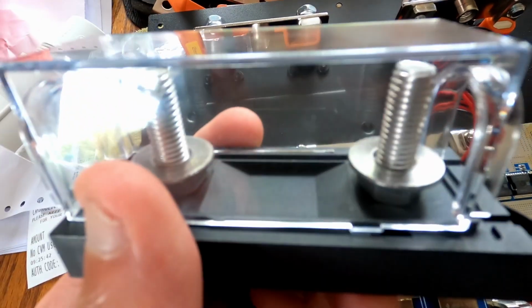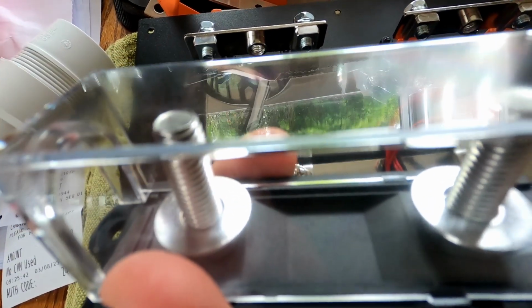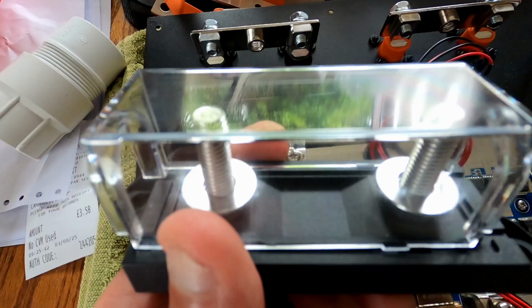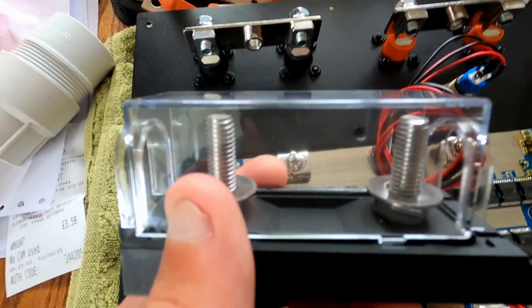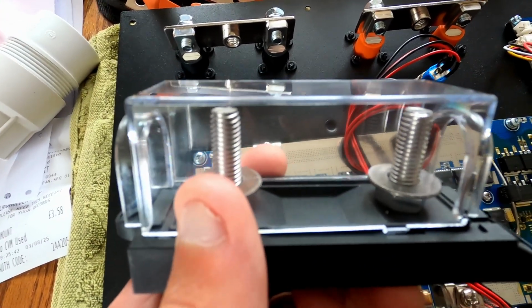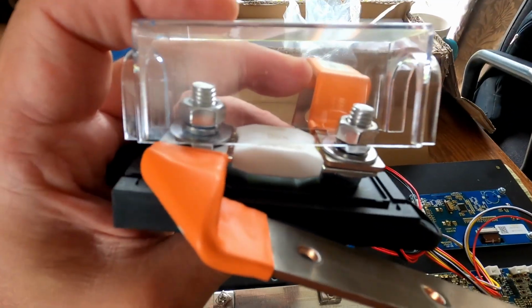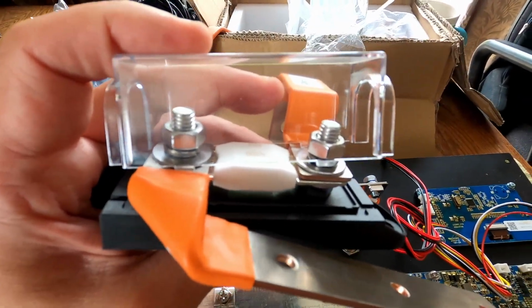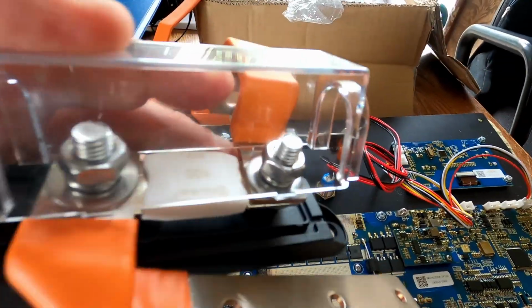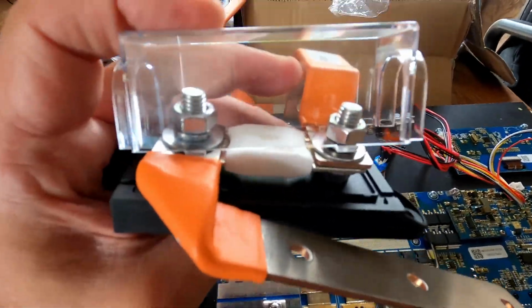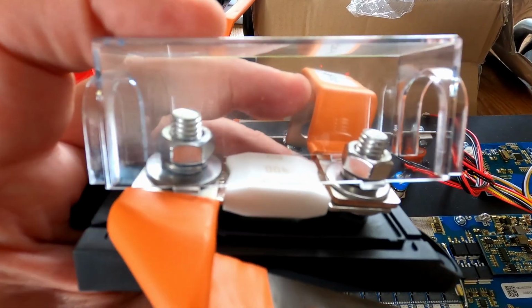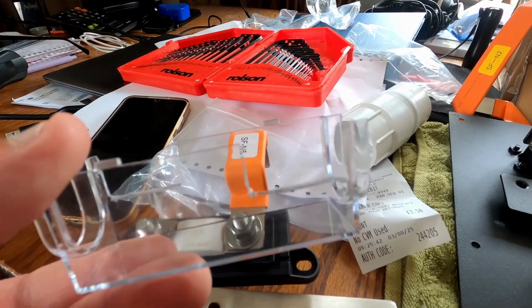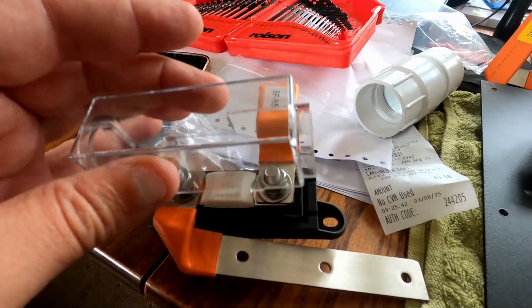We have this fuse box holder for a 400 amp fuse, which is going to go here. I can see straight away that the way the bridges are mounted on each side of the fuse, this lid is not going to fit unless I cut a hole out on each side. I guess I could use it without the fuse lid, but I like it, so I'm going to cut out both sides so I can use it, because I'd rather have it on than off. I'll use the normal grinder with a cut disc and just cut two slots out on each side, so I can now push that in and it will fit with the bridge arms that come out.